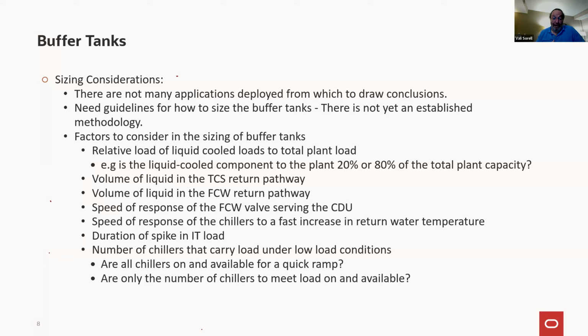And because the temperatures are dropping precipitously, with continued talk about even colder and colder temperatures, I think the buffer issue, or a way to buffer, is going to become more of a necessity. As the temperatures drop and the loads increase, it may make sense to take that buffer tank out of the TCS and put it in the facility return flow, where it can be just regular black steel or any kind of steel. It's a bigger tank because now it absorbs the buffering of all of the TCS loops. That's an important consideration. My recommendation would probably be to move that buffer tank out of the TCS and put it in the facility water loop.